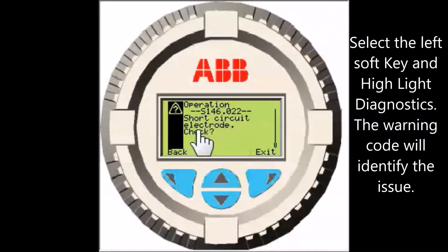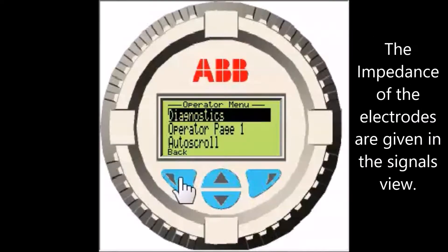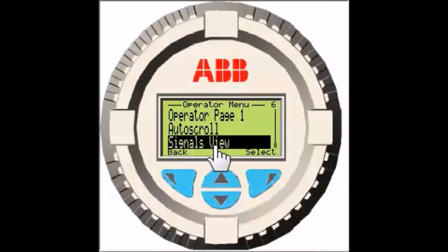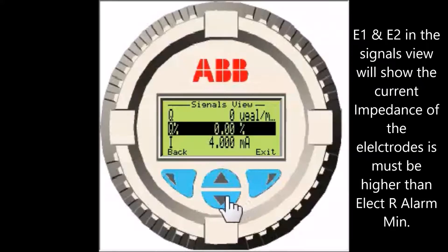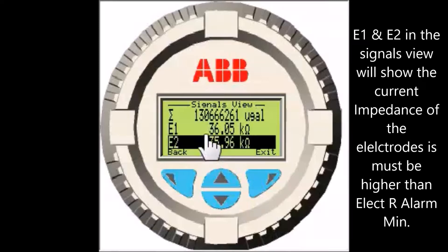Select the back soft key and return to the operator menu. Scroll down to the signals view menu and select it. Scroll to the parameter E1 and E2. These are the electrode impedances. If these impedances drop below your Elect R Alarm Min setting, it will trigger a short circuit warning. These impedances should be relatively balanced as well.